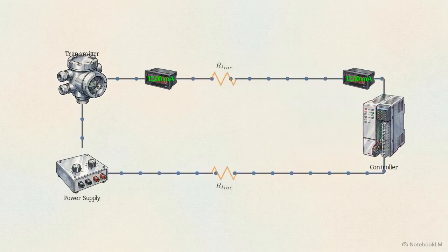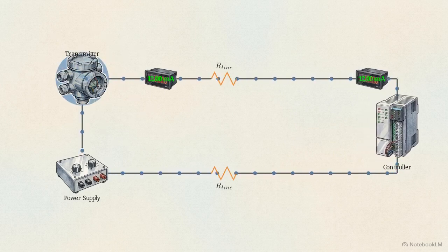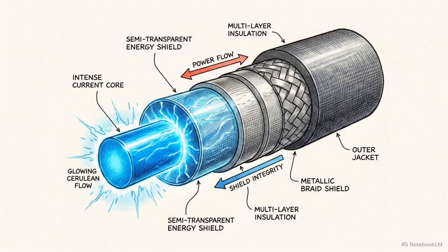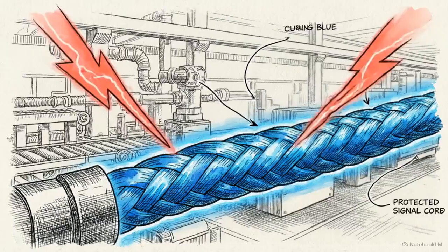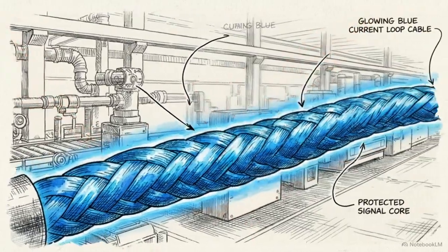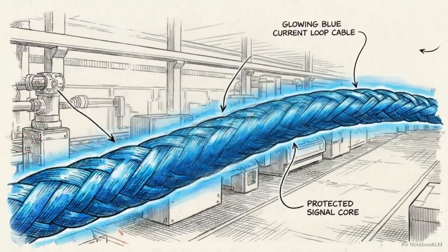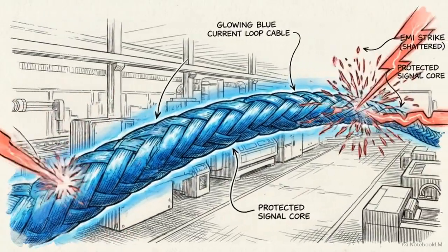If we stretch the cable, adding massive line resistance, the transmitter adjusts output voltage to maintain the exact same current flow. Because current loops operate at a very low impedance, they don't act like antennas. Any stray electromagnetic interference bouncing around the factory lacks the energy to alter the physical flow of electrons. Current loops inherently solve the two greatest threats to industrial data: distance degradation and electrical noise.